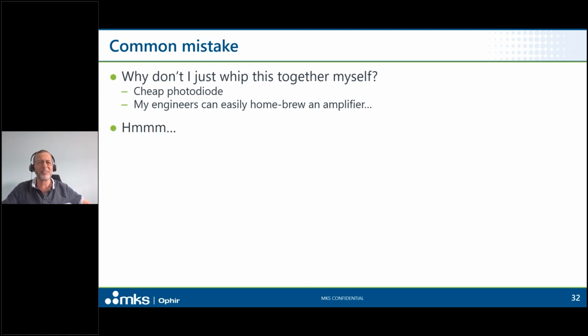But once we start getting into the nitty-gritty, then we start coming across a couple of issues. First of all, that's going to catch only changes that originate at the laser. Typical laser powers in medical applications, as I said, can be hundreds of milliwatts up to hundreds of watts. A raw photodiode will usually saturate at some fraction of a milliwatt, a couple hundred microwatts. So I'm going to need to add a whole lot of attenuation that's more than likely to introduce anomalies into the beam.